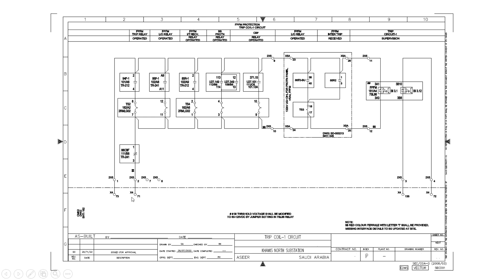In the tripping circuit, the circuit breaker's Normally Open (NO) contact is in series with the tripping circuit. So whenever this positive continuously extends to the tripping circuit and the circuit breaker opens, that NO contact will open and the positive pulse will not reach the trip coil — and the trip coil will be safe.